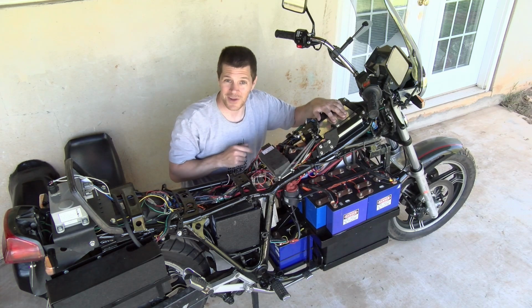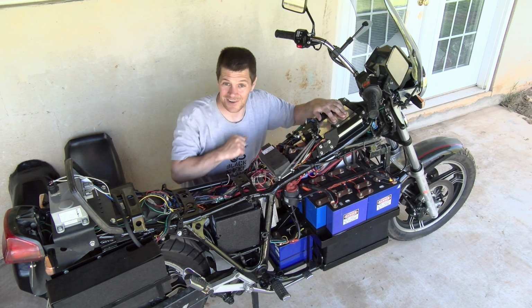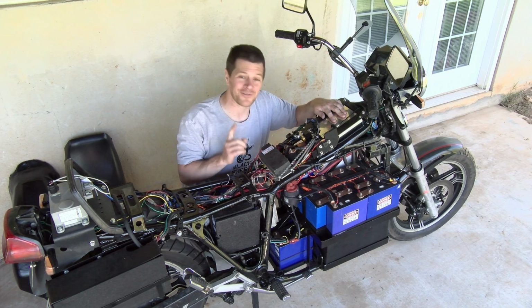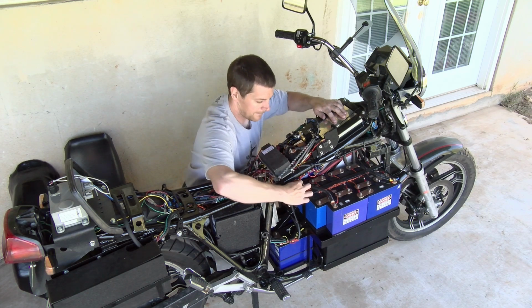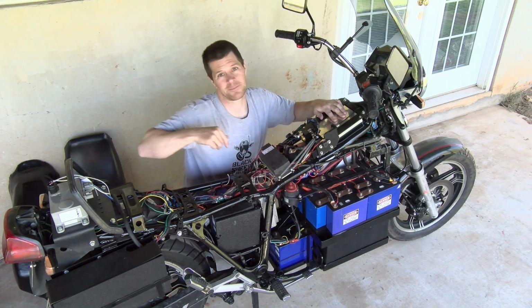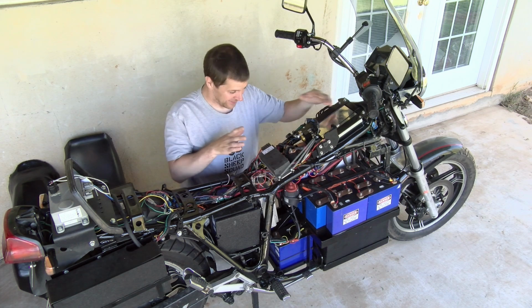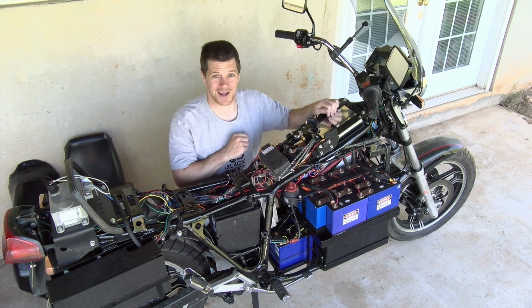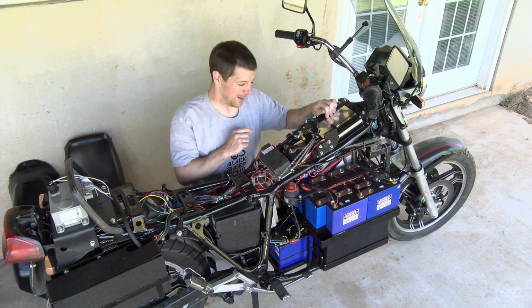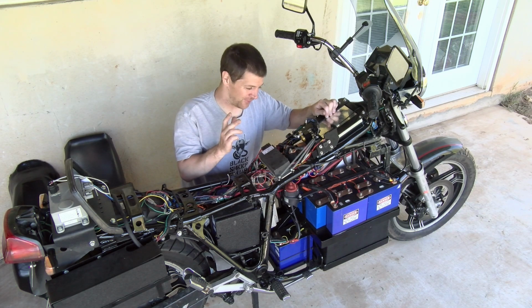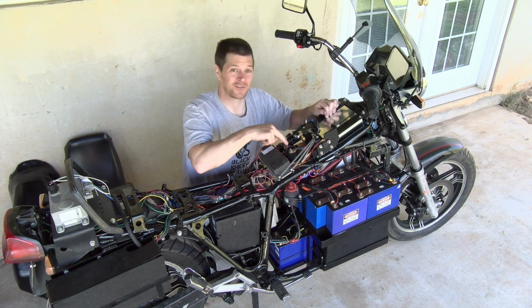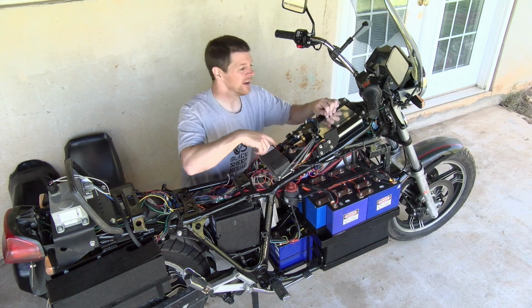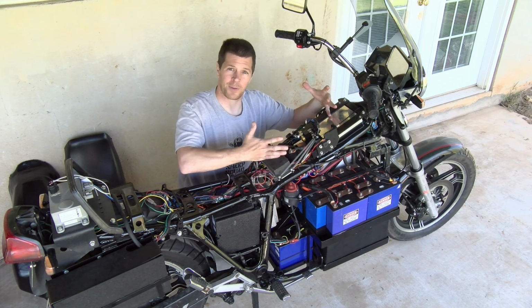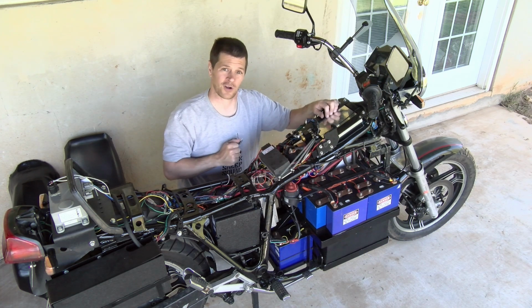You might have noticed I pulled my hand back pretty quick because I just got zapped, because I forgot to do this. That's a maintenance switch, so anytime you expose this, you ought to throw it to the off position. What I had touched inadvertently was the master contactor. So the bike doesn't always have power, it goes through a master contactor.